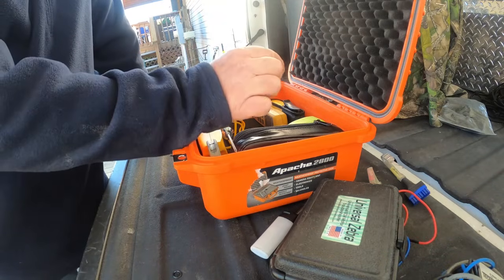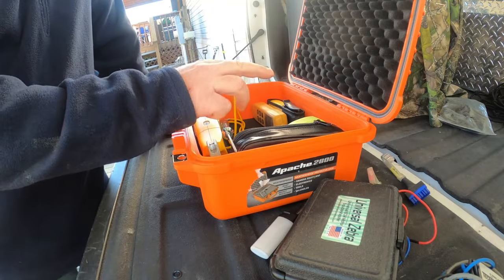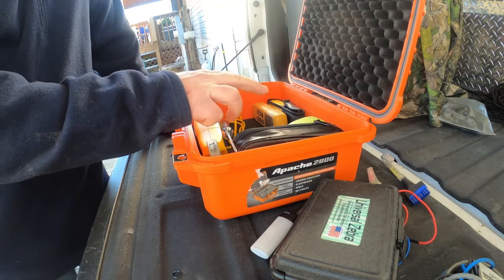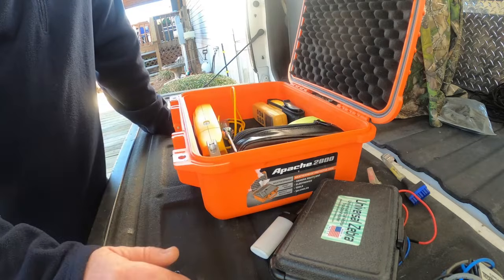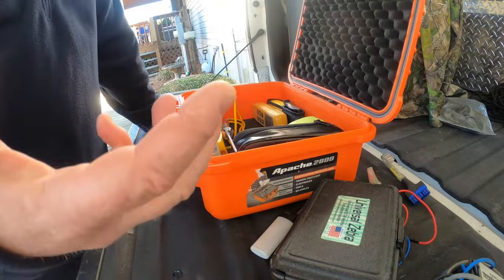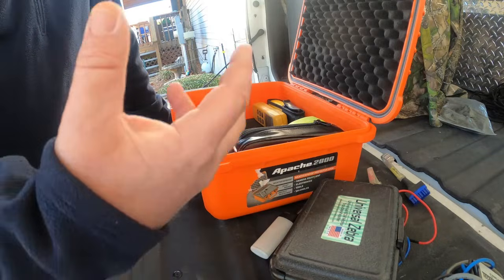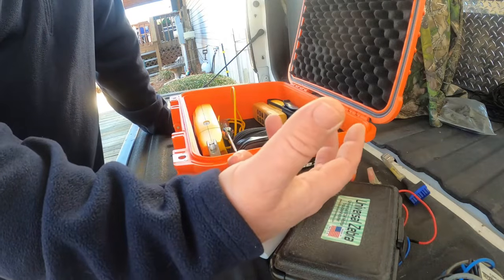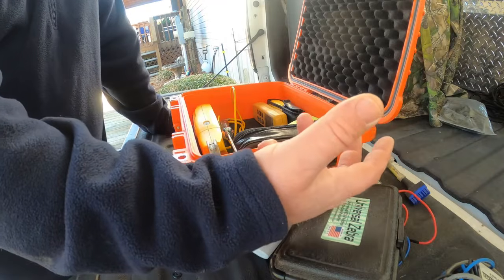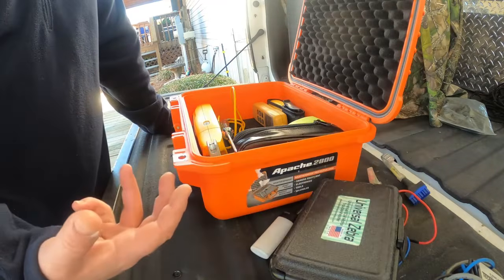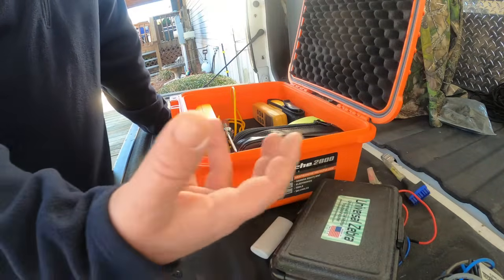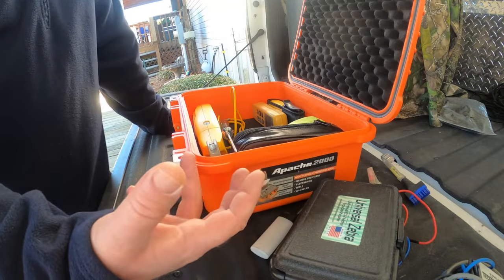There's a plug on the board. It's got 4 wires. There's 2 of those terminals you'll go between with 24 volts. The motor should come on and run. That's how you check to verify that the motor is good. Now you're going to narrow it down. Is the module on that motor receiving the data package from the board, and is it transmitting back to the board from the motor? That's the key to troubleshooting the Trane serial port motors.